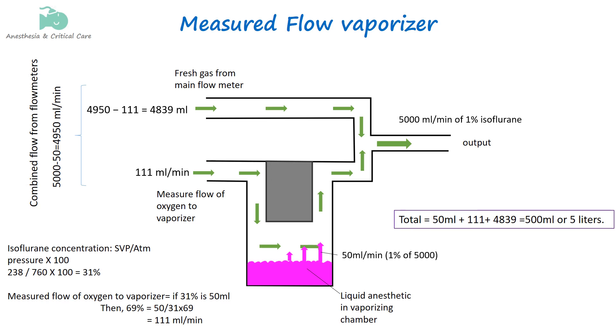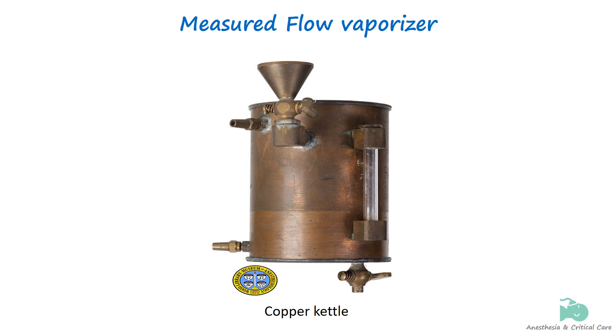This calculation is quite complex, and adjusting the flow rates of two flowmeters to precisely achieve the required anesthetic concentration is challenging at best. As a result, this method of regulating vapor output has become obsolete. The copper kettle vaporizer, introduced in the early 1950s, used the measured flow method to regulate vaporizer output.